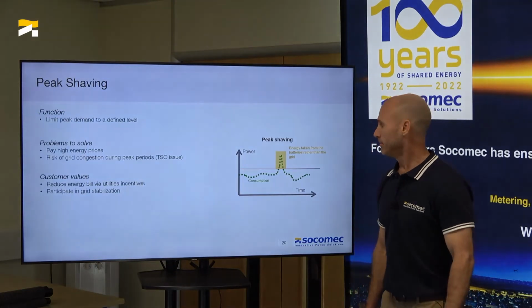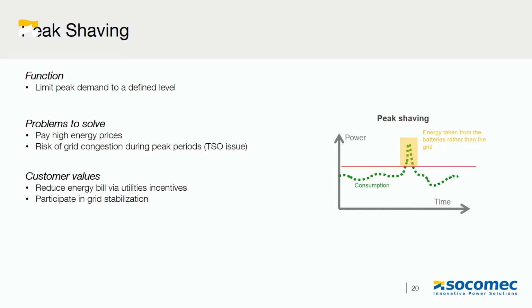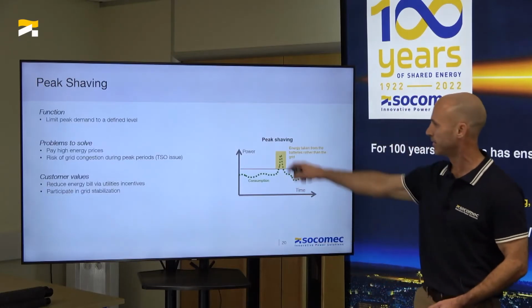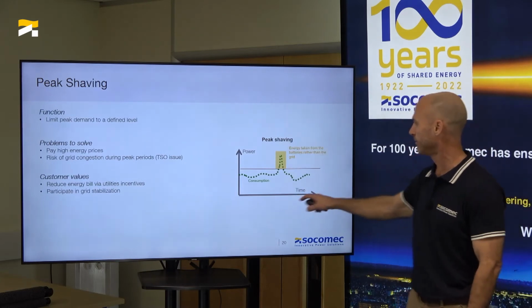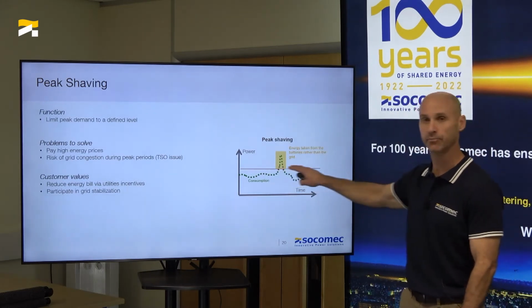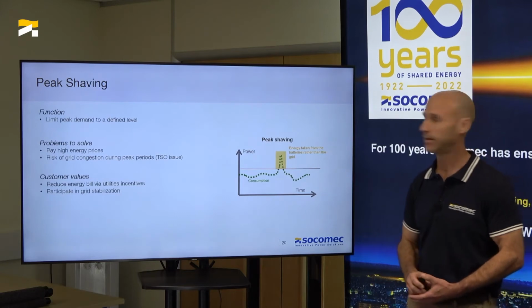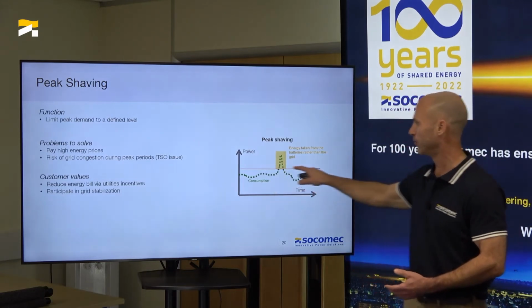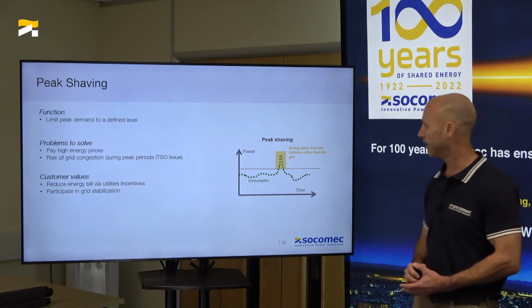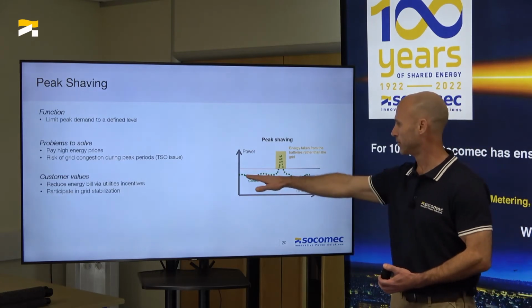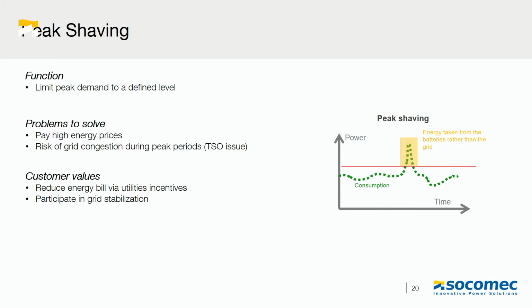Okay, so on to peak shaving, money saving. This isn't a new concept, it's been around for many years, and it's basically where we make use of a secondary power source to carry you through your peak demand periods. Looking at this graph, you've got a limit which could be set by your energy provider, and exceeding this limit would result in energy penalties. So your consumption falling over and above that limit is taken out of the batteries rather than from the grid.